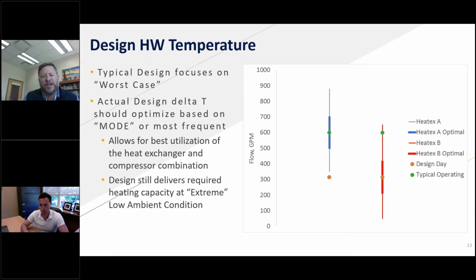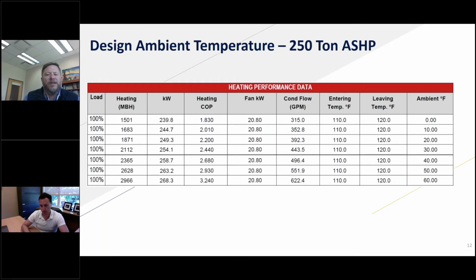Even if it gets colder outside, we just elevate the condensing temperature and we have a smaller window. If we think back to what I'm talking about here, we're seeing a wide range. I stopped at 60, but you might have an air source heat pump system that's going to be providing domestic hot water. So I start looking at that. Well, now it's got to run at 80, 90, even 100 degrees outside. And we have a really, really wide range of what that unit is going to see for its low side pressure, or what we're seeing on the low side. And so what that means is we have a wide range of what the capacity in that unit can be.